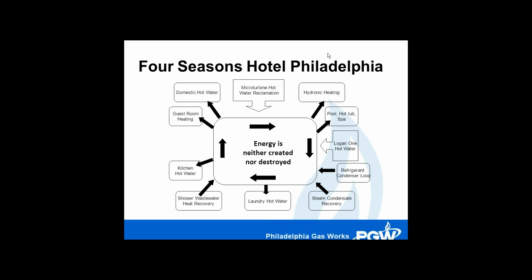When you look at this sketch, you'll find it's like a loop. You start with heating, and when heating is satisfied, you go for domestic hot water. If you satisfy domestic hot water, you go for the kitchen, then the laundry, and keep going. When you get to the point where all the heat recovery coming out of the turbine or CHP system is used effectively, that's where you maximize your savings.